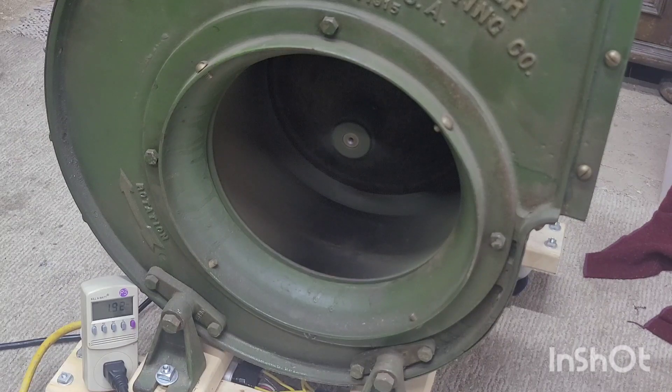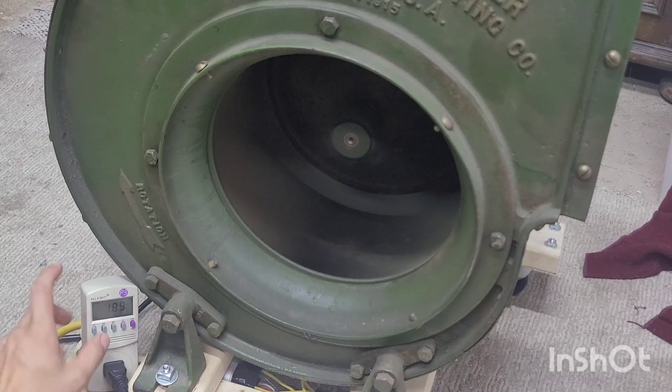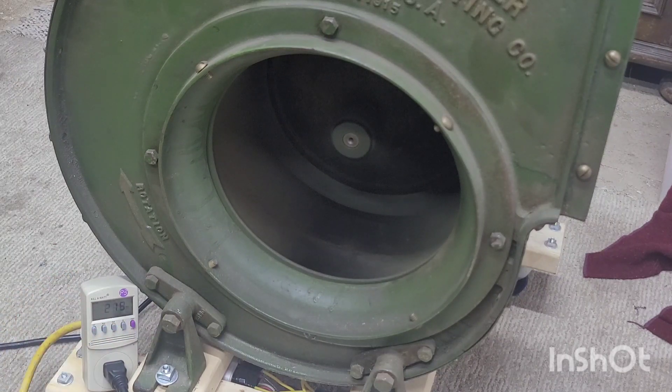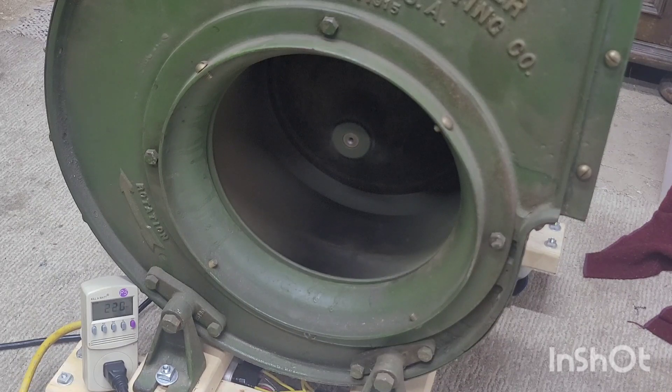You can see we're back up to where we were for current, or I should say back down. 1.92 roughly. And again, power factor 0.95, watts 219. It's basically 220, pretty much the same where it was because nothing's different now that it's running. The start capacitor just helped give it a faster start. So now I'll just turn that off.